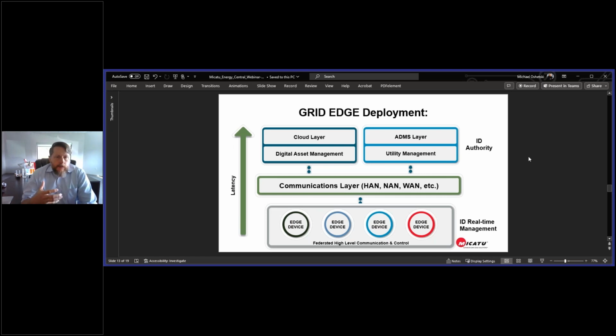So when we put this into a federated edge, we can also tell it to behave differently based on the situation and based on previous learnings. For example, you may be able to sectionalize on detection of a tap within wave cycles, versus having to do a trip, reset, or whatever the previous operation was. You can even do it within half wave cycles—that's where we're heading with this. And now with this new edge deployment, it gives us the capability not only for higher resilience, but we can also deploy this into actual energy savings.